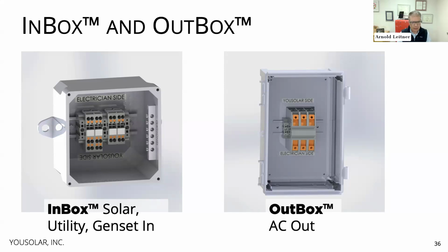These are high-low solar, L1, L2 for AC input. On the right-hand side it's L1, L2, neutral and ground. We decided we don't want any tightening mistakes here, so all of these are spring-loaded Phoenix connectors. We set them all up for 200 ampere or 400 ampere. The electrician just opens the box—something they're familiar with and like to use—sees L1, L2, L3 labeled, and connects the PowerBloc to the load.